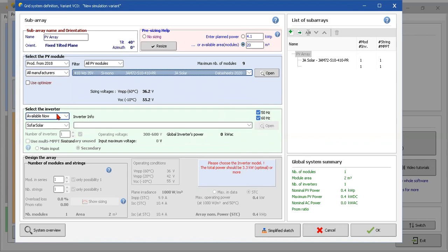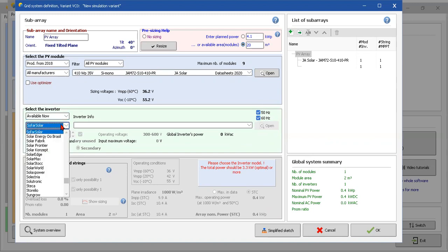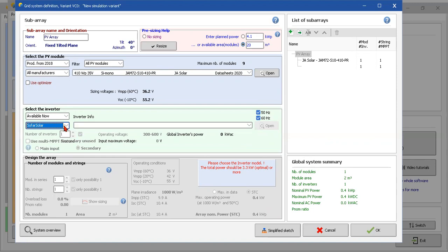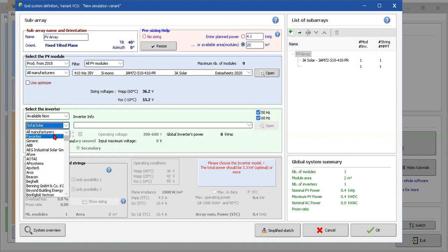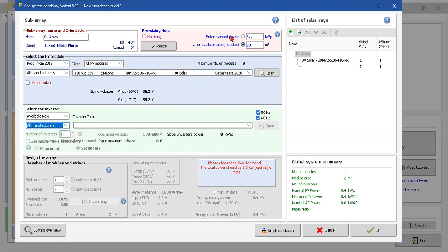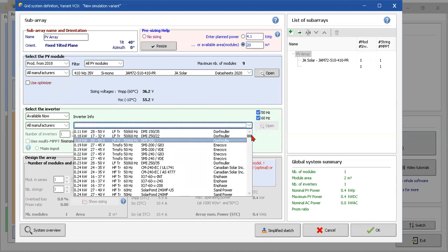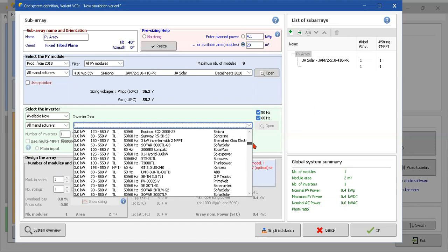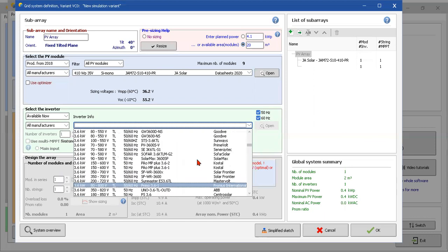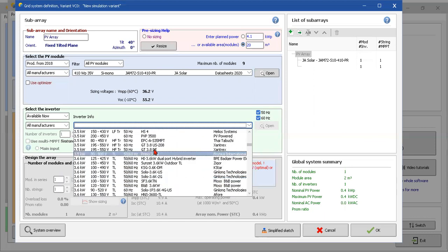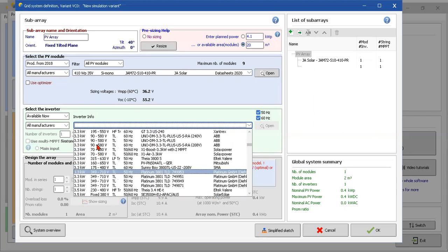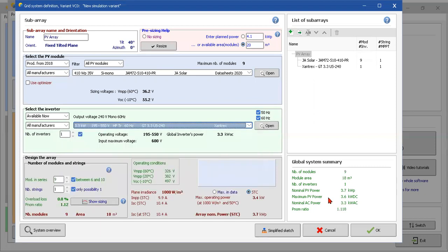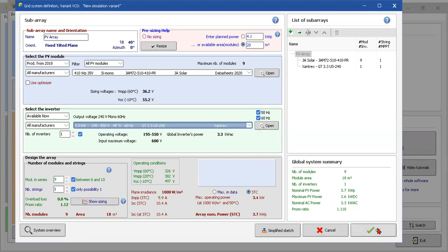Now the inverter. We have here the inverter. Yes, and the plane power is 4.1, but there's some losses. So the system says please choose the inverter model - the rated power should be 3.3 kilowatts or more. Of course we can choose a bigger inverter, but we're gonna spend money without using it - we're just gonna lose this money. So the idea is 3.3. For example, this one. Okay, Xantrex 3.3 kilowatt. And here we have nine modules in series, which has one string, so we have just one inverter. Okay, that's fine.